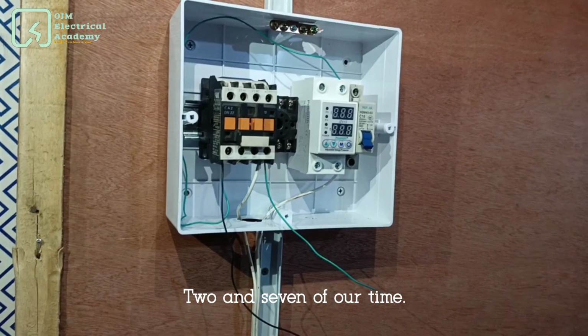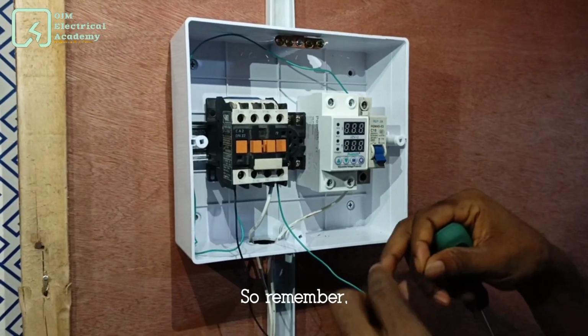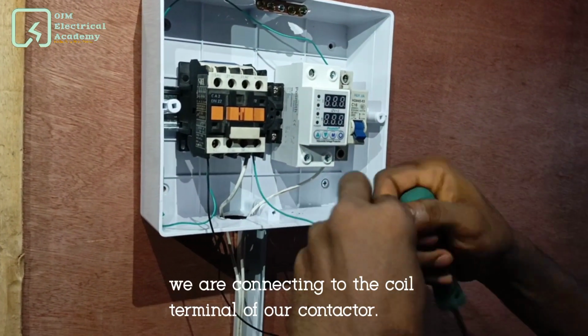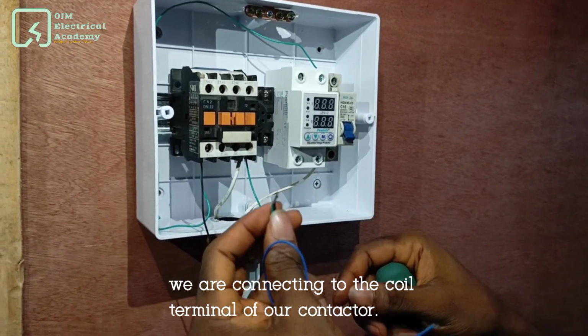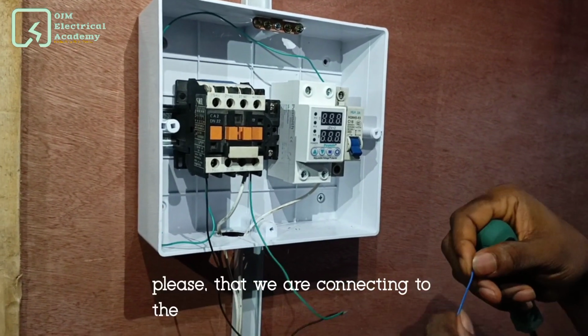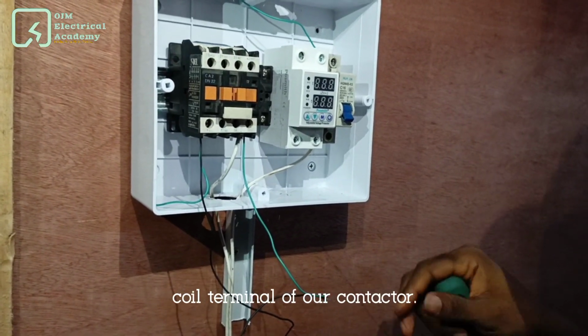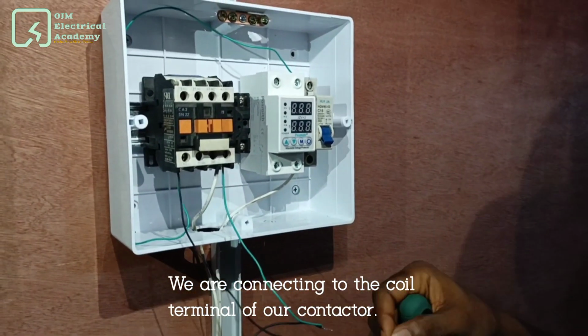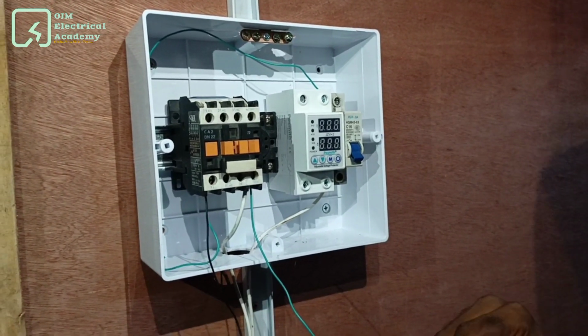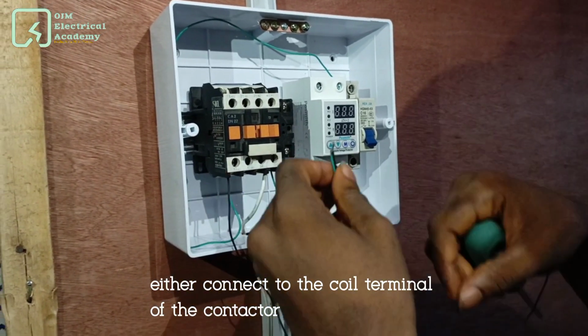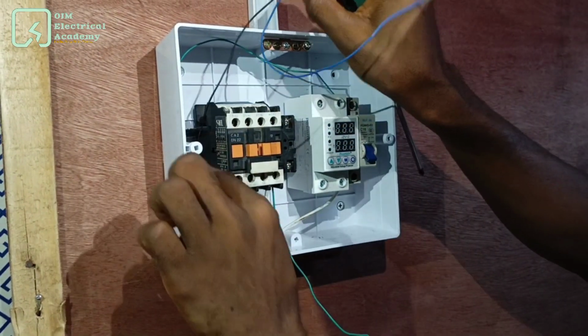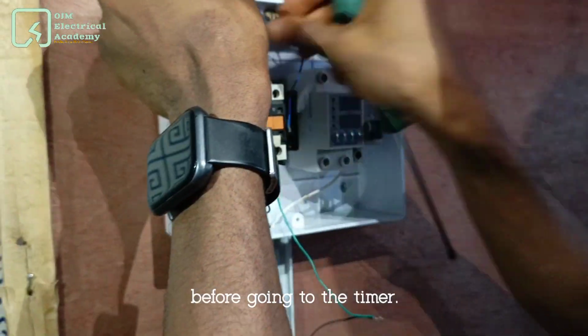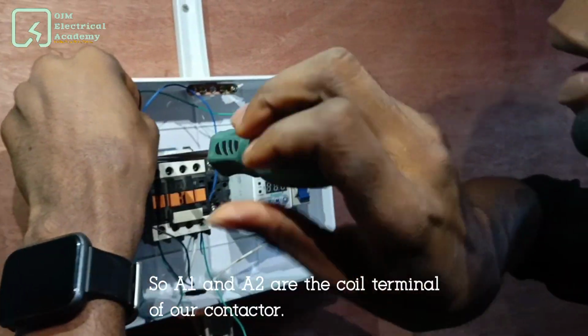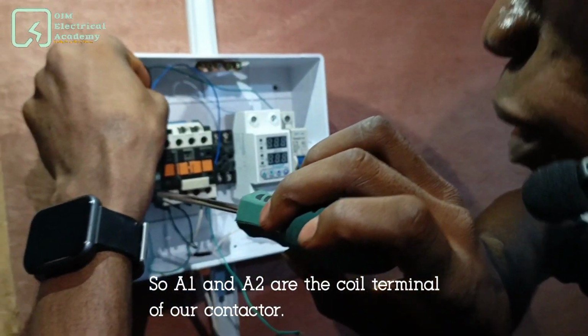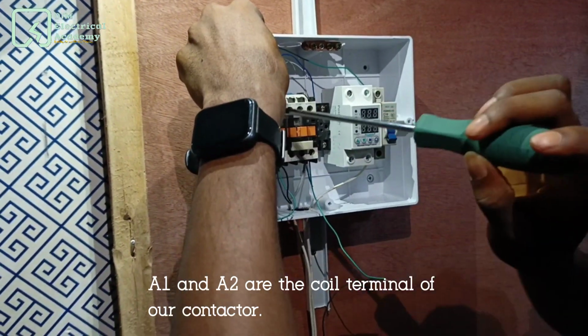So let's quickly make the connection to 2 and 7 of our timer. Remember, as we're making that connection, we are as well connecting to the coil terminal of our contactor. We can do it either way, either connect to the coil terminal of the contactor before going to the timer. A1 and A2 are the coil terminals of our contactor. So I'm connecting to A1.